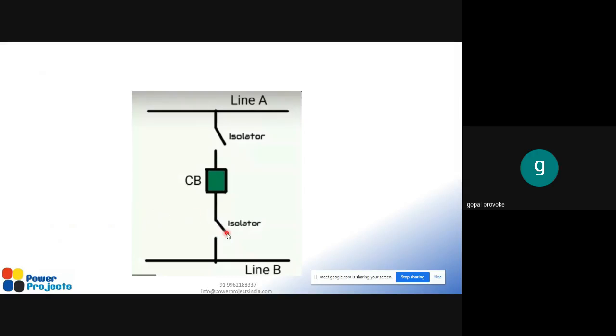So for example, if we first close this isolator and this circuit breaker, and then at last close this other isolator, since the breaking capacity of this isolator is less and it is an off-load switch, when we close it there will be arcing in this isolator, and this arcing will damage it. But by keeping the circuit breaker open, when we close this isolator, there won't be any problem.